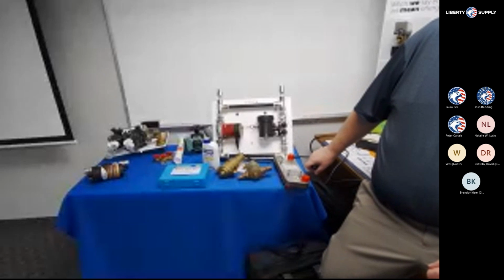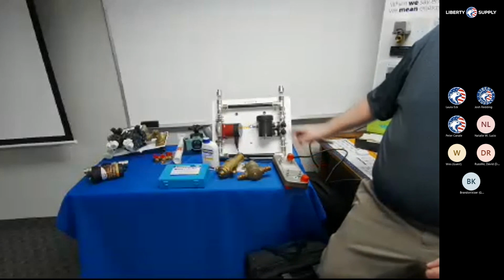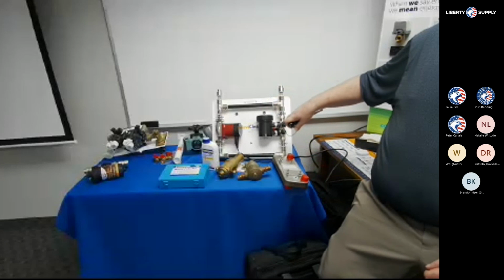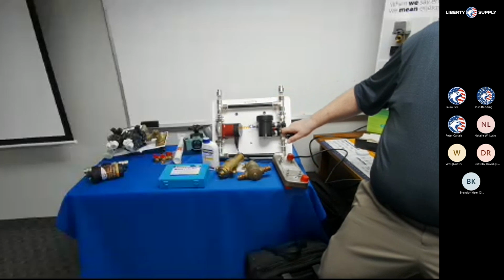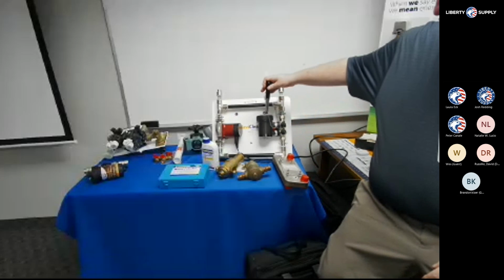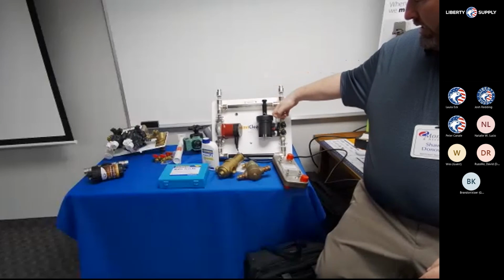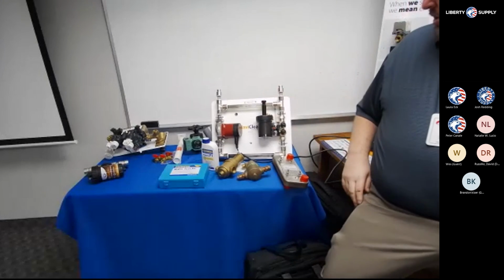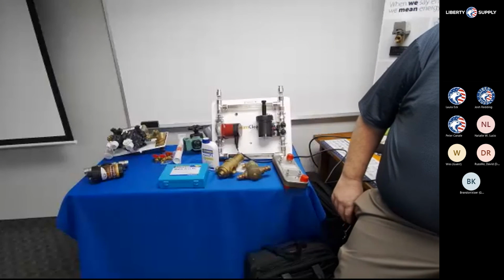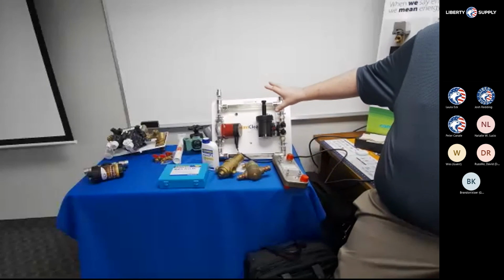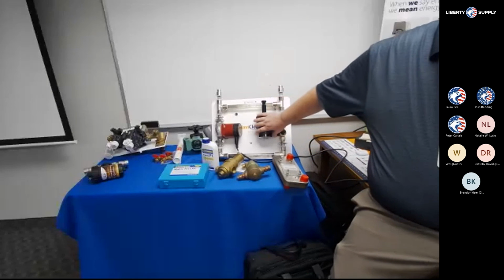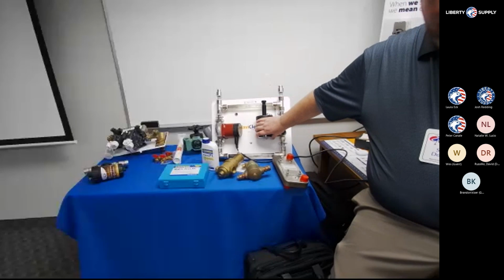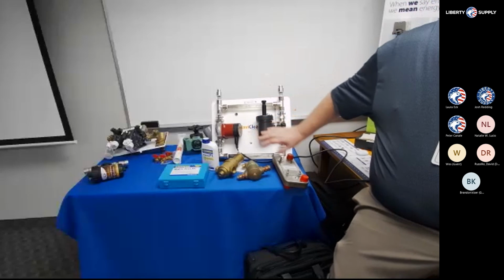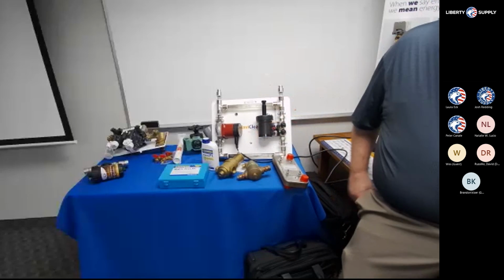When we do that, we're going to be able to see how much of that system changes into the black fluid. Now you're seeing the iron oxide has escaped the filter. It's back out in solution. As I put that magnet back into the system, you can see it's now being reabsorbed, and over time you'll see it get clearer and clearer, because now we're holding all of that iron oxide inside of this canister.